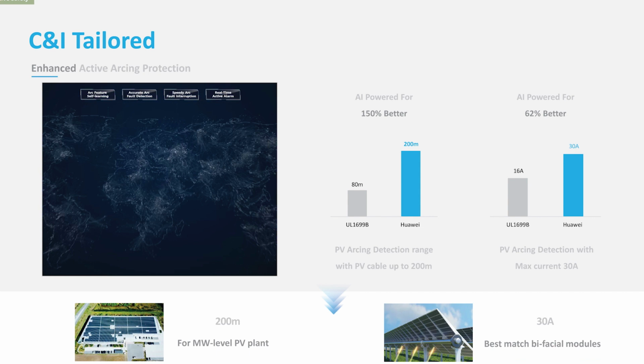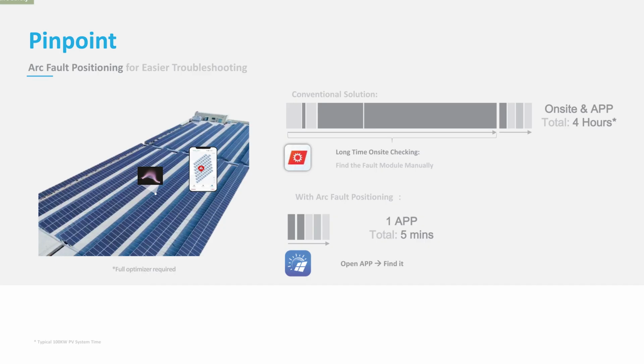So we can do 150% better than any competitor because we can detect an arc up to 200 meters. A standard solution can only detect up to 80 meters. That's one of our competitors. We can also detect an arc of up to 30 amps, and our competitors can only do up to 16 amps, okay? Okay, so this is just an example. You can also pinpoint where the arcing happened. So the monitoring system will tell you string number 10 had an arcing fault. We switch the inverter off. Then your technician can go to string number 10 on the roof and locate the fault. In other solutions from competitors, you have to find a needle in a haystack. Okay.